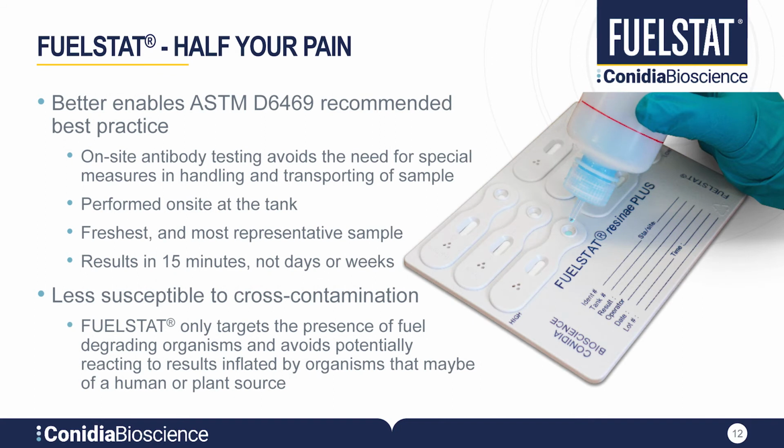FUELSTAT continues to be different from a number of alternative tests in that it can be conducted in its entirety at the location the sample was originally drawn from, without the need for capital equipment, sterile facilities, or other consumables. It also provides results in minutes, not days or weeks. As it can be performed so quickly and on site, it reaps the benefit of using the freshest and most representative fuel sample possible, helping it adhere to the recommendations laid out in ASTM D6469.